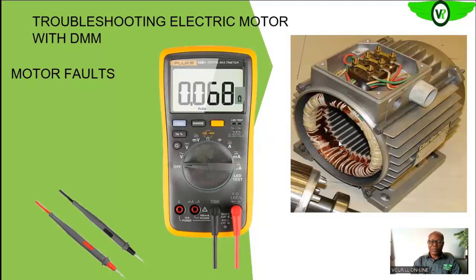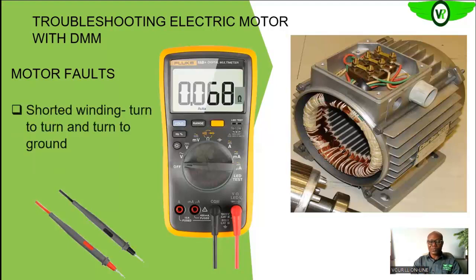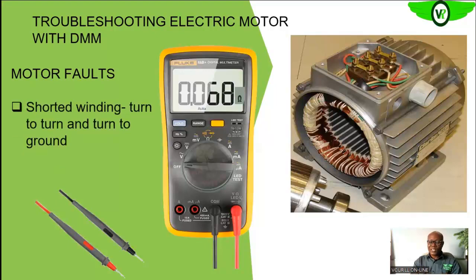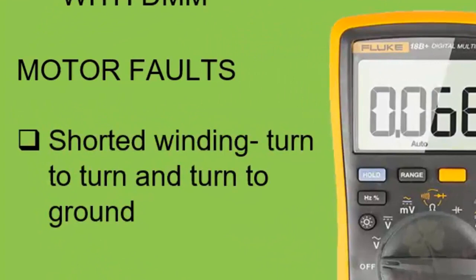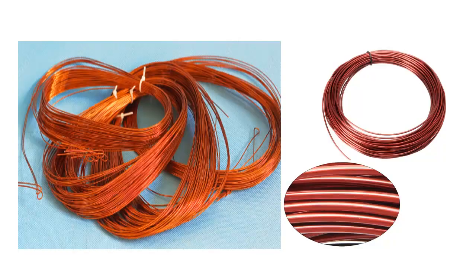So now, what are some of the major faults that you could experience with the electric motor? Some of the faults you will experience are shorted windings, turn-to-turn shorting and/or turn-to-ground shorting. Now, when we say shorted winding, what do we mean? We know that when you are winding the motor from start to finish, you expect that whatever current is flowing through that winding should only have access out at the finish point of that particular winding.